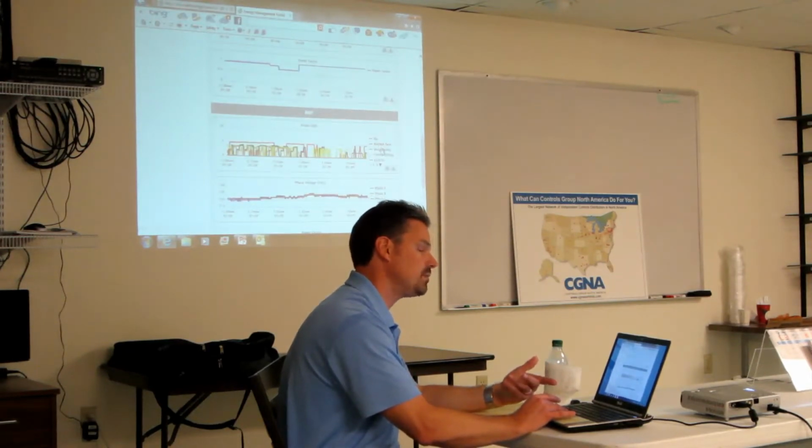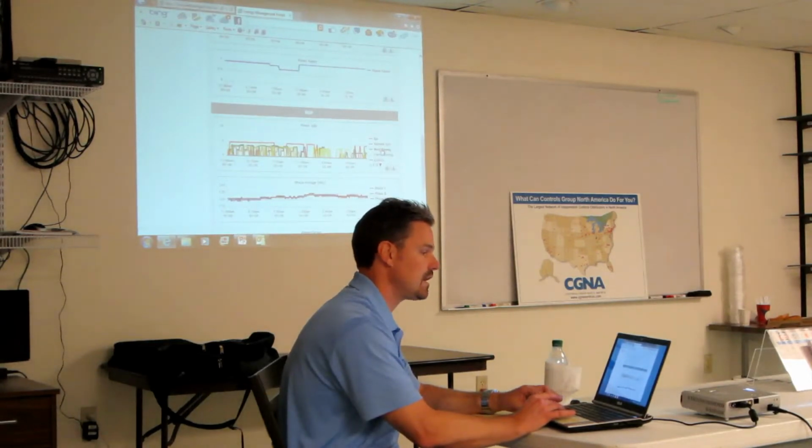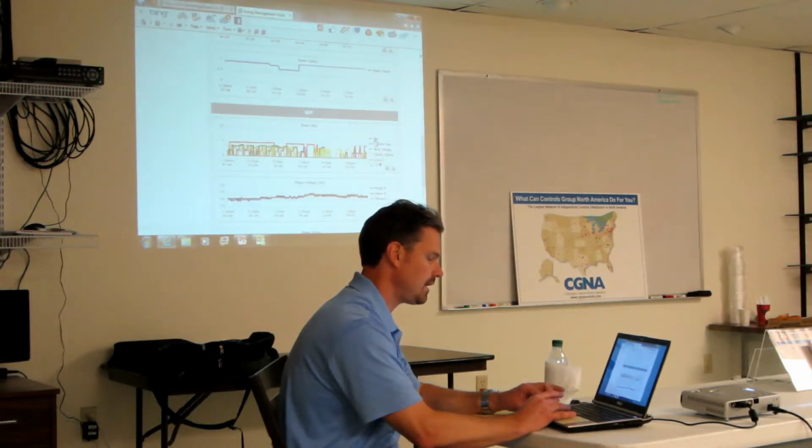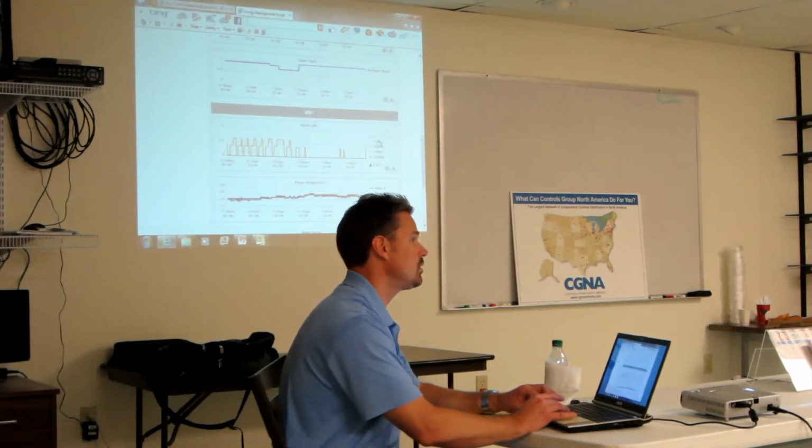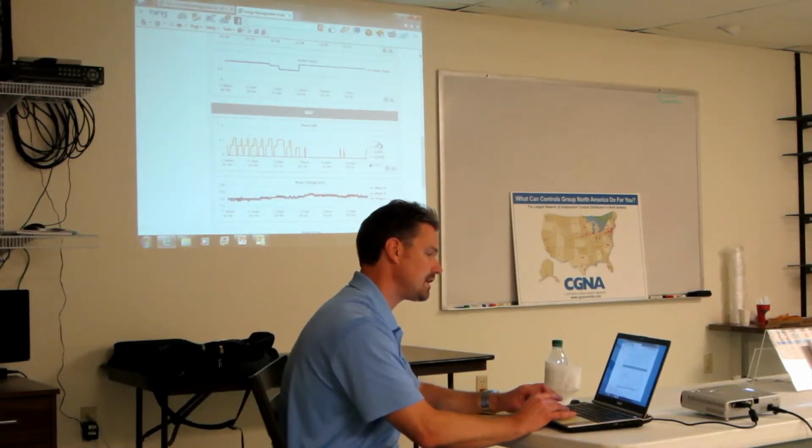And so all of these can be named whatever, when you're setting this up. But you can see there's a bar unit, kitchen, east, west dining. Okay. And again, if you want to isolate just one, you can do that. Or that's 2 actually. All right, so whatever load 5 is, that they know what that is, then they can see the energy for it. You can see which ones are drawing energy overnight, during vacancy.